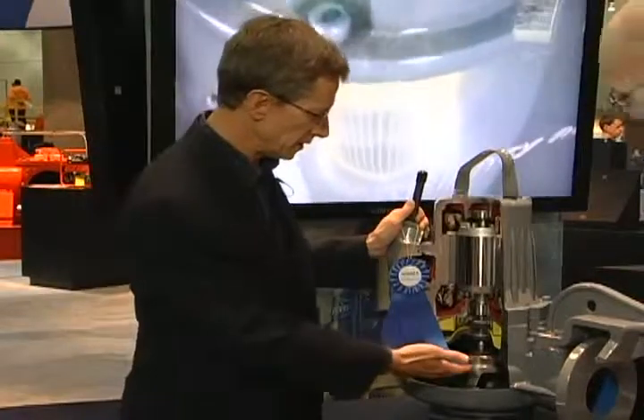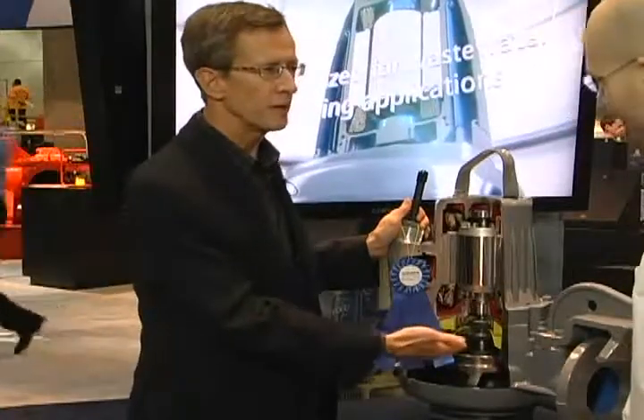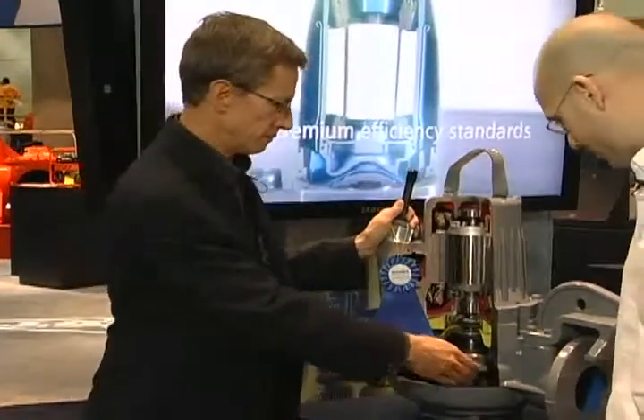And this shows the latest innovation within the Flygt N technology. It's what we call the adaptive N. And it's really a Flygt N pump where the impeller can move on the shaft up and down. So when a bigger piece of solid is entering the wastewater pump, instead of getting squeezed underneath, the impeller is lifting momentarily and allowing the solids to pass through. So it's really an innovation that adds to the features and the functionality of the N hydraulic.